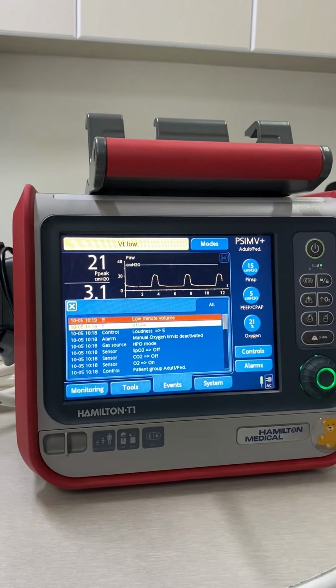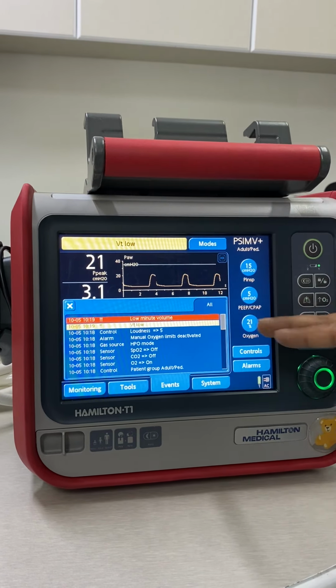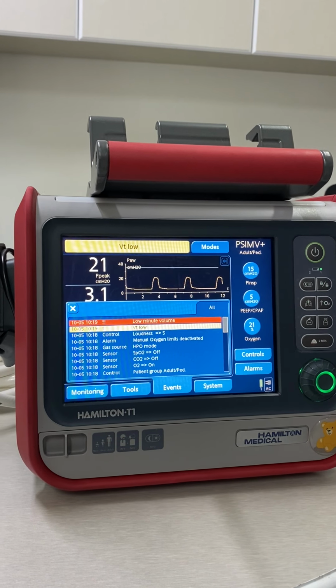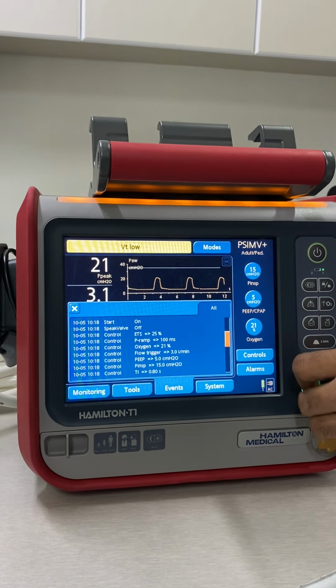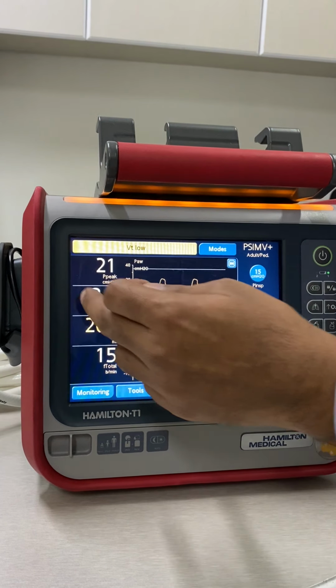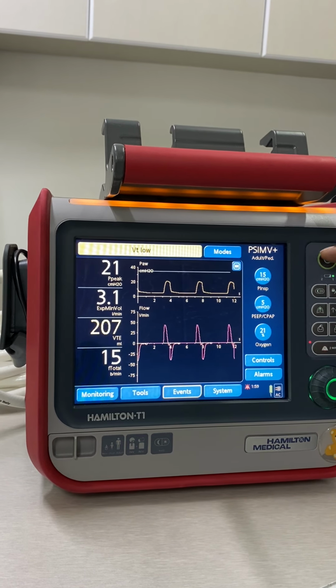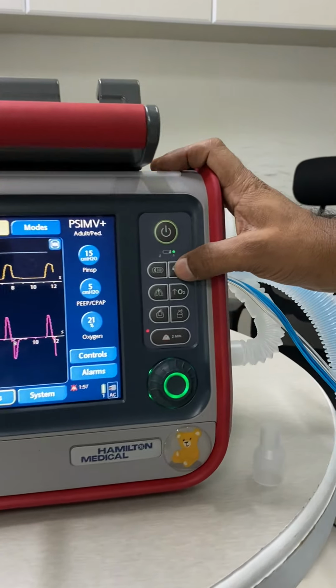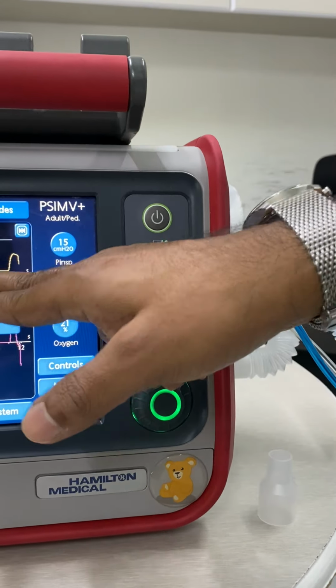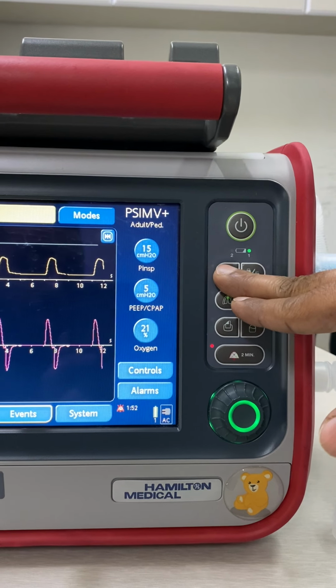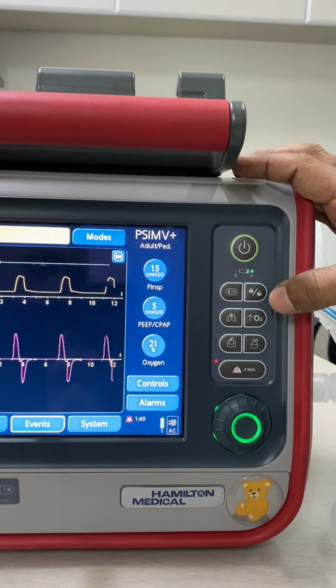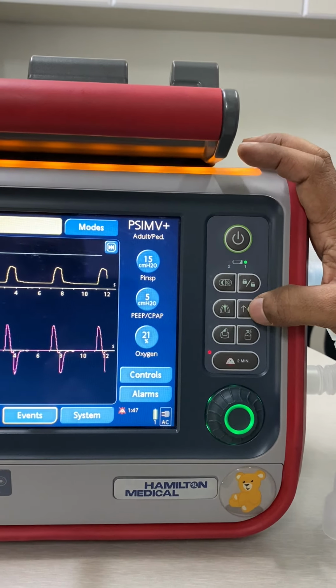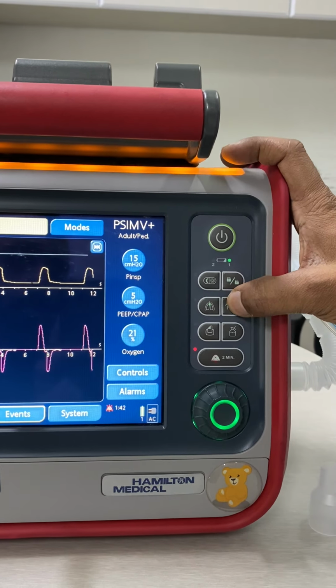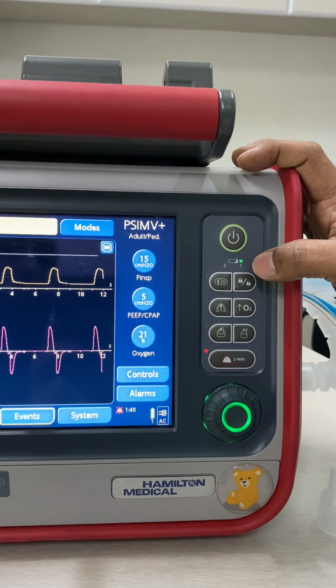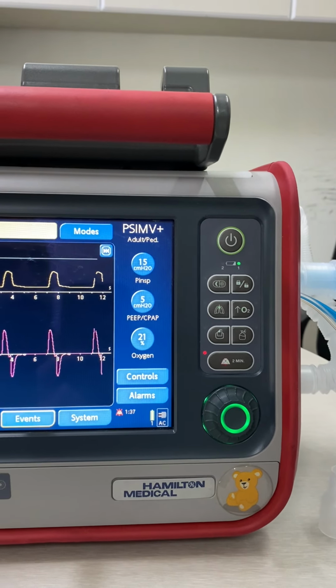And also you can go to the events where you can check the settings and the alarms which came for the last 1000 events, all the settings and all the alarms. And we have some soft buttons over here. You can see the lock screen, you can lock the screen, and also this is for the brightness, but it's not configured now. And we have the O2 flushing for 100% O2. If you press it here, it will give 100% O2 for 2 minutes for the pediatric adult group. If you have chosen the neonatal, it will be plus 25%.